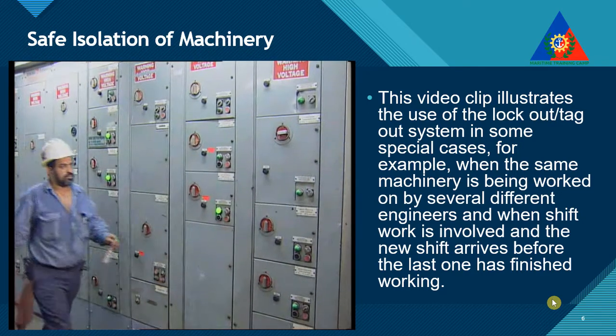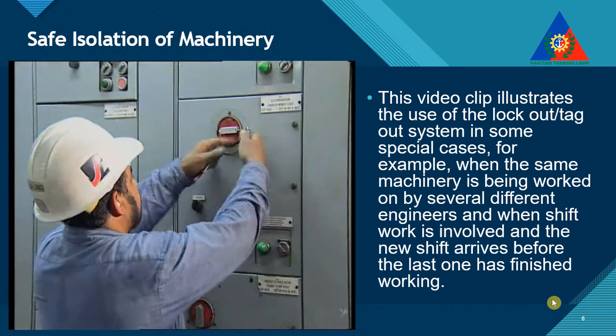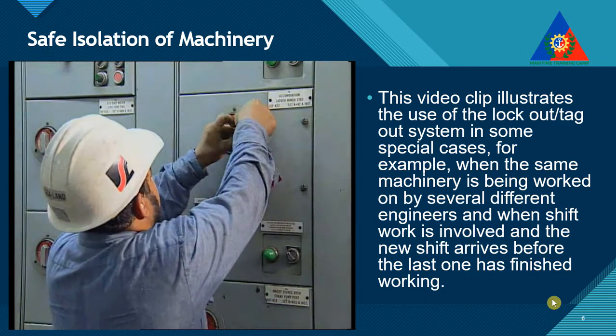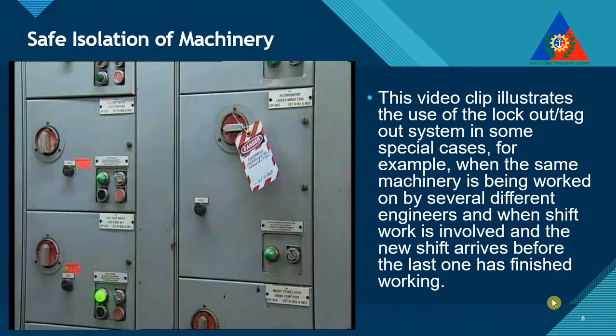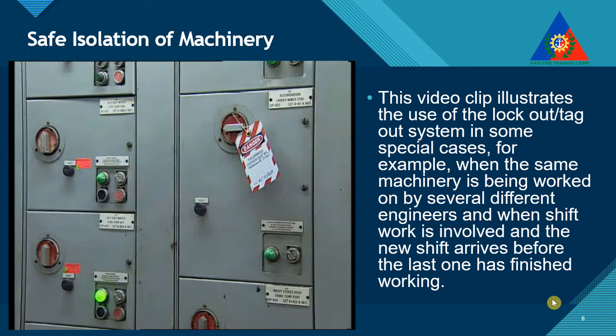The second tier of safety, the physical prevention system, is operated when the isolating device is locked in the shut-off position with the key removed and a warning tag placed on the device. This is to ensure that the system cannot be reconnected without the active approval of the keyholder. The tag in this case informs everyone of the details of the keyholder, and sometimes the circumstances of the shutdown, as well as serving as a warning that the system is being worked on.